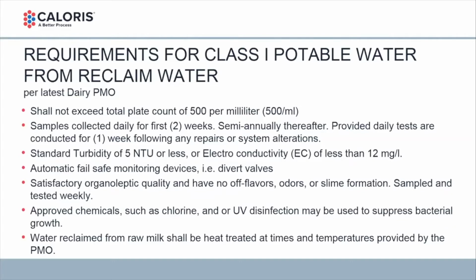To meet this requirement, you need to not exceed a total plate count of 500 per milliliter. Following commissioning, you need to collect samples daily for the first 2 weeks, meet the standard, then semi-annually thereafter. And this is provided daily tests are conducted for 1 week following any repairs or system alterations. So say you have a UV light for disinfection and you need to repair or replace a light, you need to collect these samples for a week again and pass all the tests.